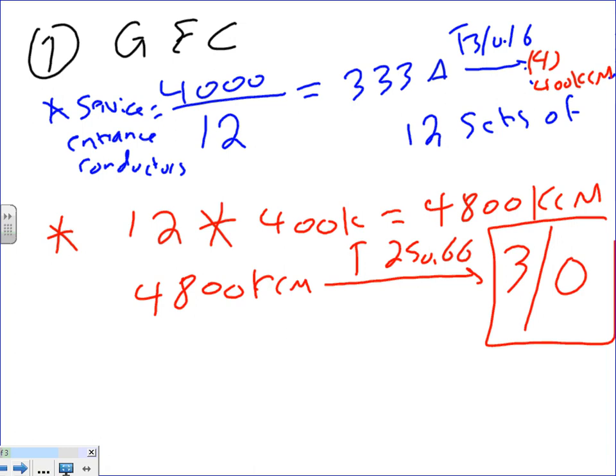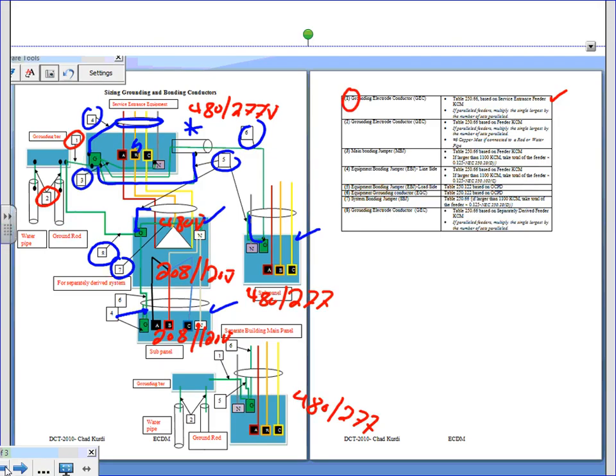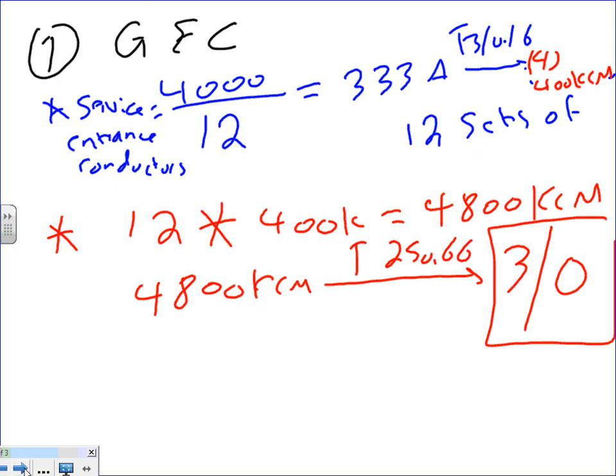Any question, guys? Any question about the grounding electrode conductor? Everybody know where this conductor is located on the graphic that I gave you? Four conductors? One conductor, yes. One conductor, this is right in here. We're sizing that conductor right in here. Okay, one conductor. Good point. Maybe I should put one conductor here. One conductor, 3 aught. Any question, guys, about the grounding electrode conductor?